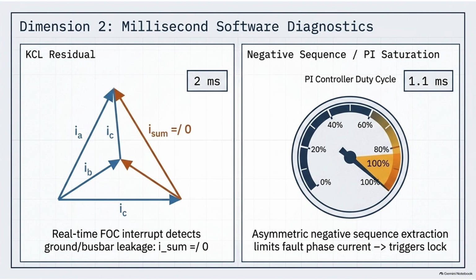Okay. In a perfectly operating three-phase motor, the current flowing out of the phases must equal the current flowing back. Mathematically, phase A plus phase B plus phase C must exactly equal 0. And if it doesn't equal 0, the current has found a shortcut. It's leaking to the chassis ground. Right.